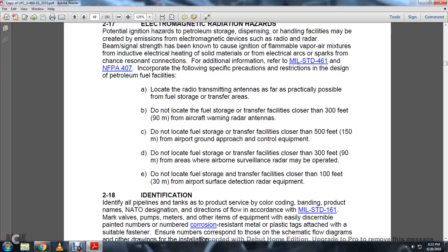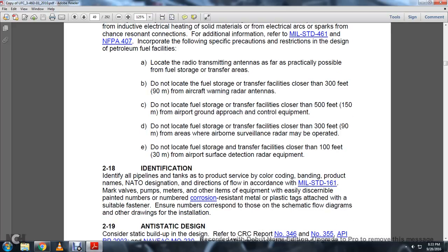Do not locate the fuel storage and transfer facilities closer than 500 feet from the airport ground approach control equipment. Do not locate the fuel storage and transfer facilities closer than 300 feet from the areas where airborne surveillance radar may be operated. Do not locate the fuel storage and transfer facilities closer than 100 feet of the airport surface detection radar equipment.